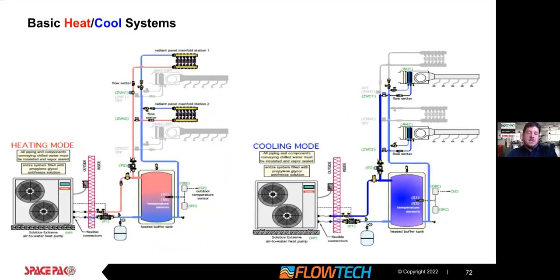Getting into a little bit more complexity, one of the beauties of the units is they're doing heating and cooling, and this is showing a basic heat cool system. You got your unit feeding a buffer tank, and in the wintertime, you're running it through radiant floor heating or panel, floor panel or wall panel in there. Summertime, flips over into cooling mode, running it through an air handler, SpacePak air handler, or conventionally ducted air handler in the cooling mode, and you're keeping that water temperature chilled. I should mention too that what we're seeing too, radiant now is becoming optional with a lot of projects.